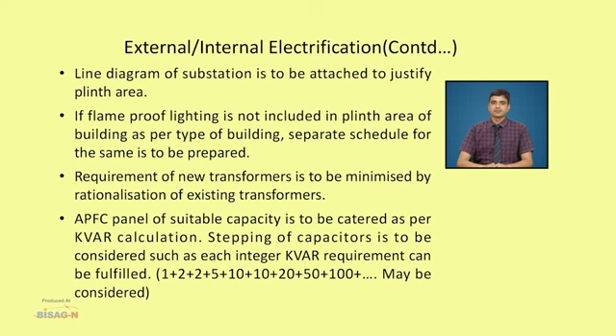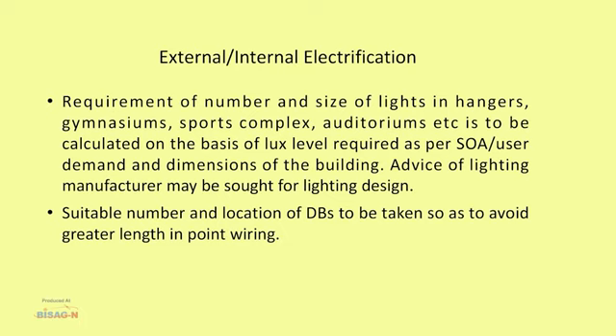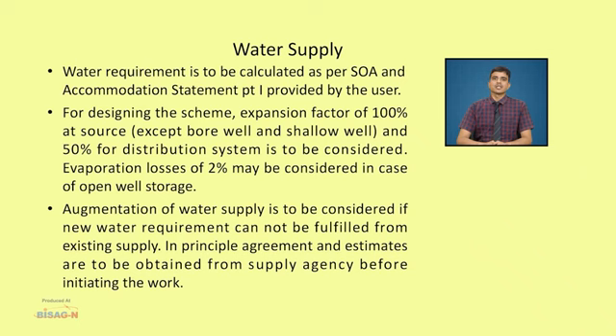Requirement of number and size of lights in hangars, gymnasiums, sports complex, auditorium, etc. is to be calculated on the basis of lux level requirement as per scale of accommodation or user demand and dimensions of the building. Advice of lighting manufacturer may be sought for lighting design. Suitable number and location of DBs are to be taken so as to avoid greater length in point wiring. Now comes the water supply. Water requirement is to be calculated as per scale of accommodation and accommodation statement part 1 provided by the user.